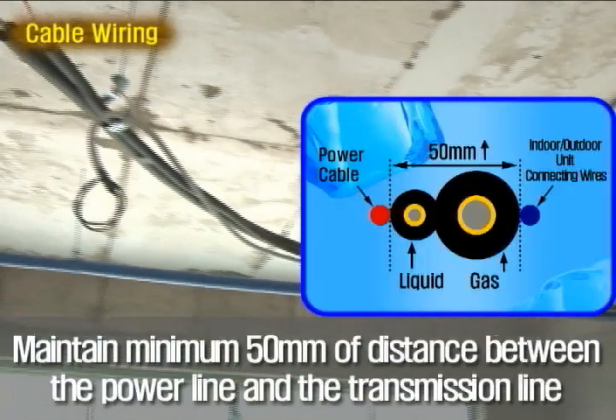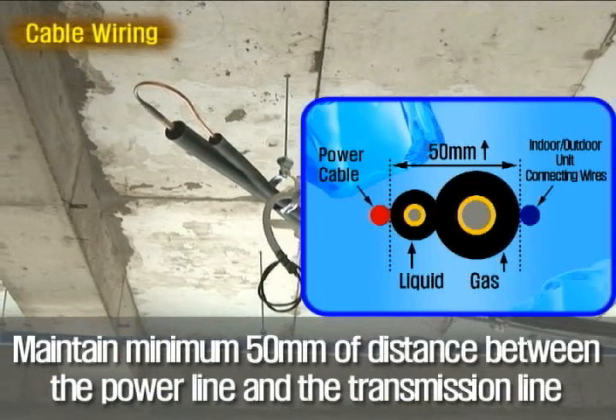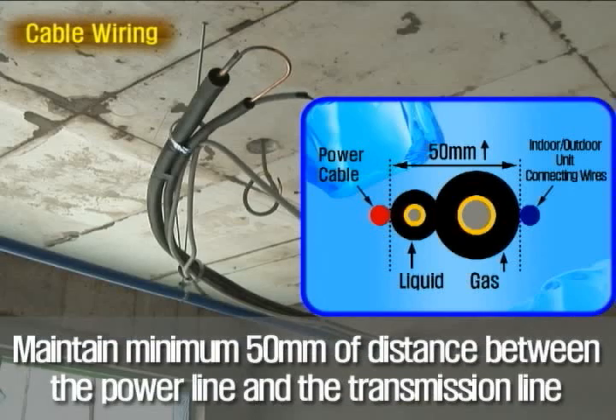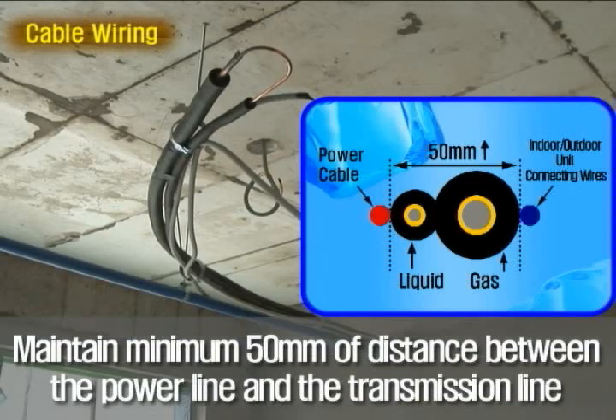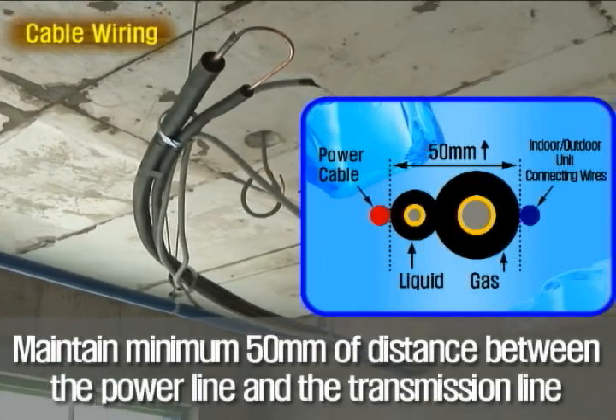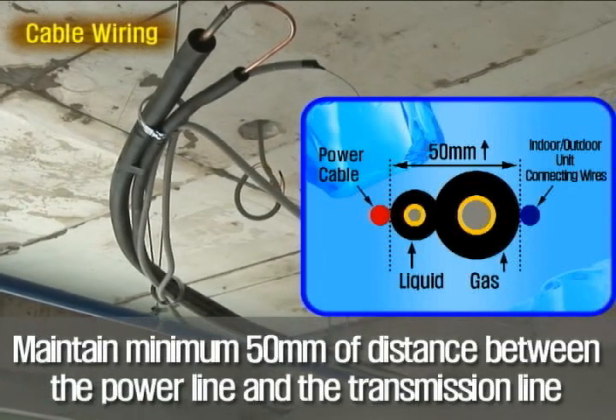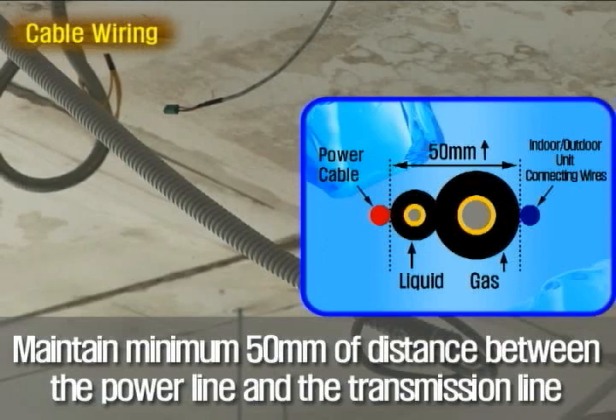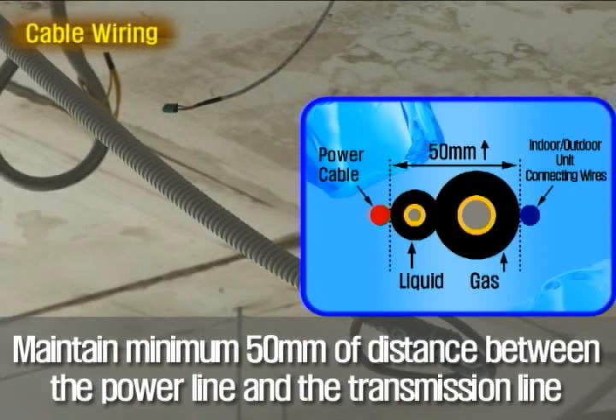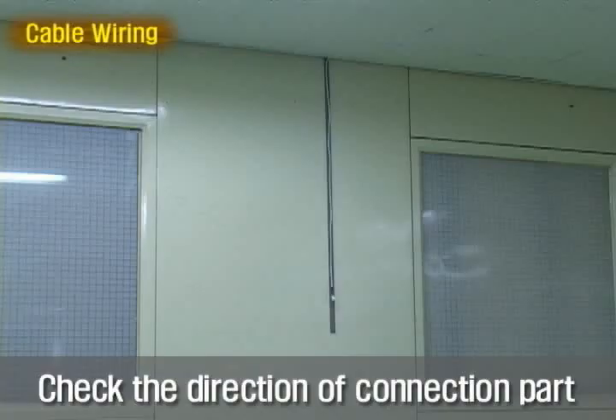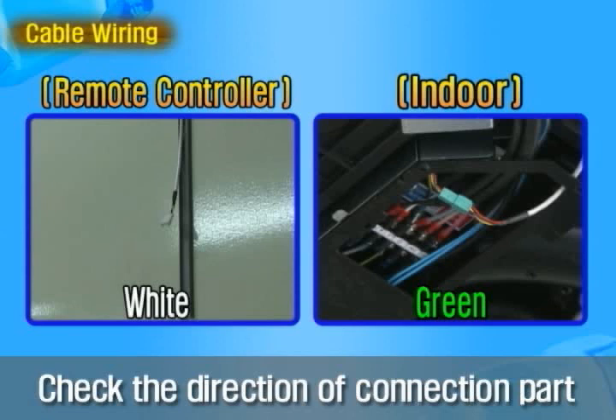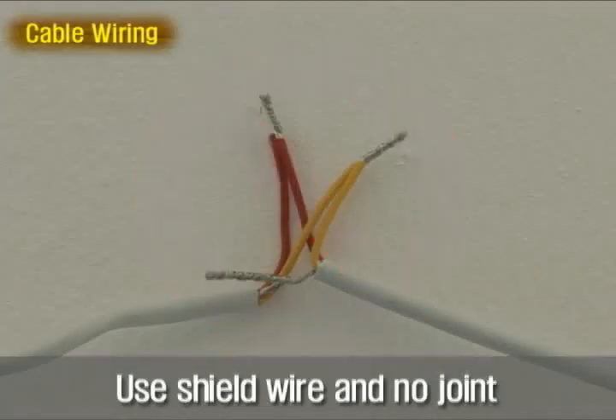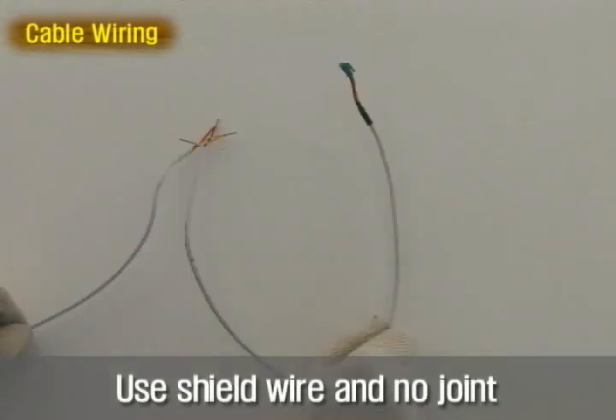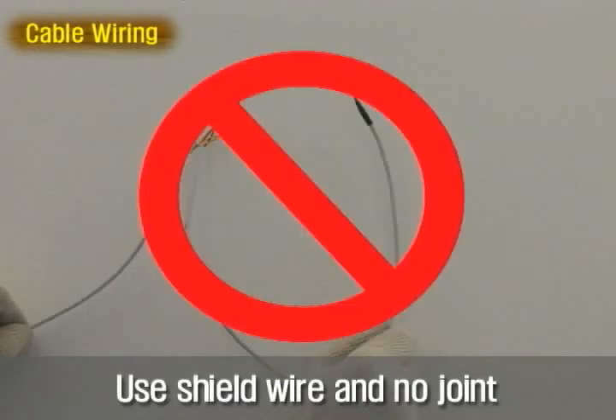If you install the power line and the transmission line close to each other, there might be defect in the system because of the noise. That is why you must keep at least 50 millimeters of distance between them. Therefore, you should not put the both lines into one tube. Fix the remote controller wire with cable cover, and the wire should not be connected reversely. Remote controller should use only one cable without a joint on the way to prevent electrical noise.